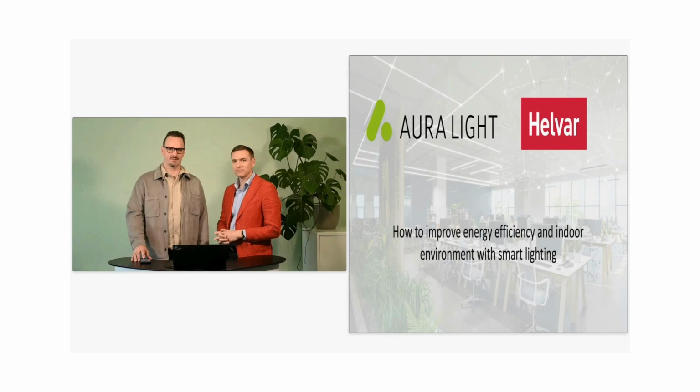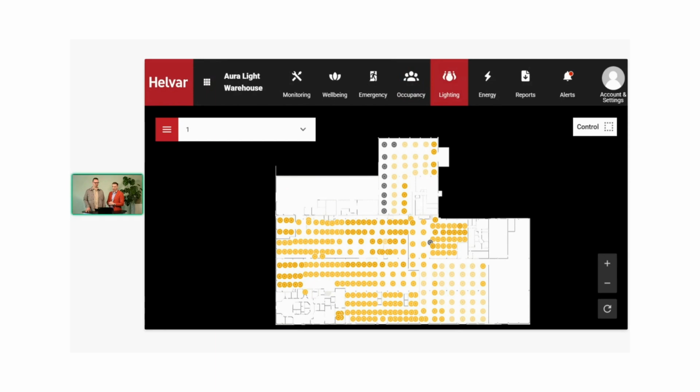Naturally, there also is lighting, as it should be. It's a lighting control system, so we also get the data on what the light output level is on each luminaire. Here you could also remotely see that, hey, there are lights on while there should not be. The example I gave earlier on the sensors being false triggering would be visible here, for example. And I think already there was one location here where you saw that there is a heat pump next to it. So you are going to change the location of that sensor so that it's not triggering, for example, during the night when the heat pump goes on. Yeah.